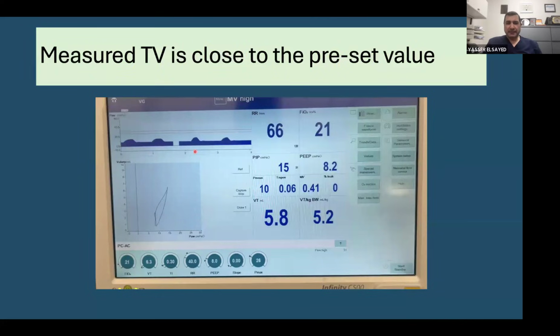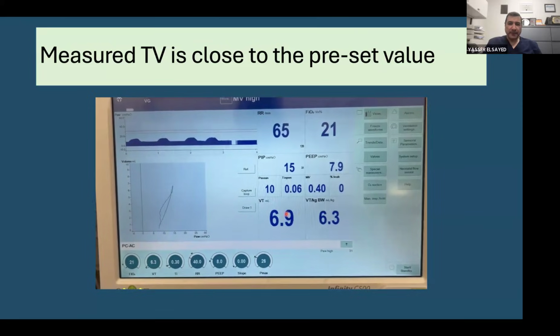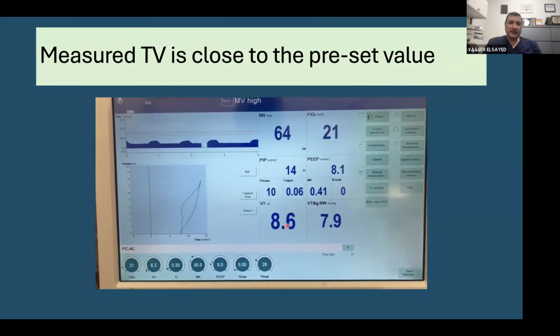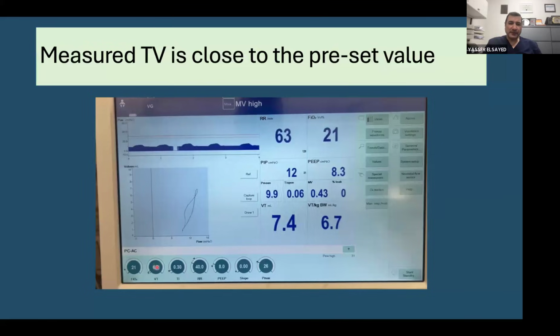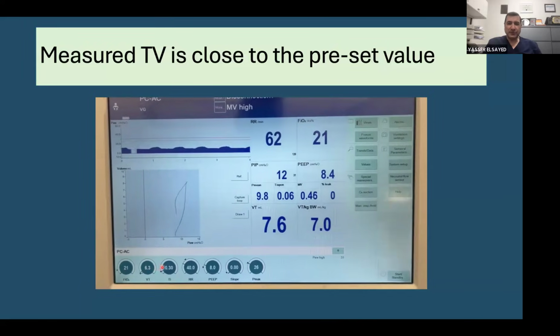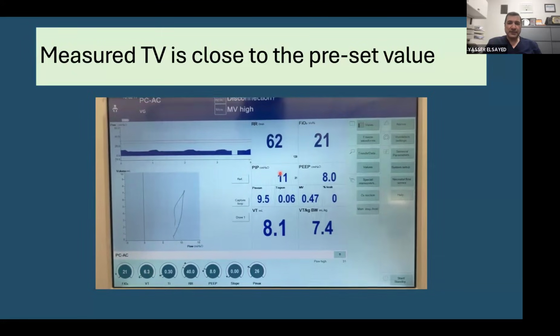Now let me give you this example on your machine, assuming this machine is available in most of the units. You can see the number here is the tidal volume, 6.3, and the number on the screen is 5.8, which is the measured. So you have the preset, this number is fixed, and you have the measured tidal volume, and you have the PIP needed to deliver this tidal volume. These numbers will help you understand if the compliance is good or not. So let us see. Most of the time the measured number is either above or matching the preset, so we have good compliance, and the PIP is just a low number.